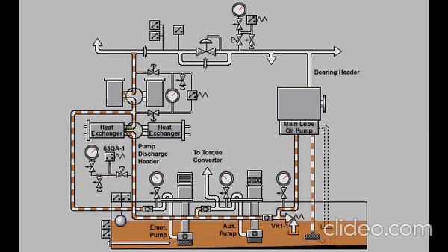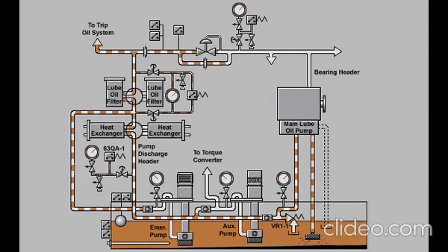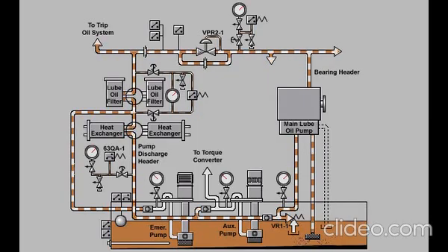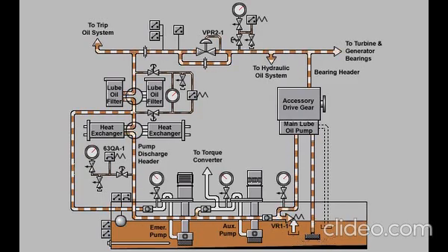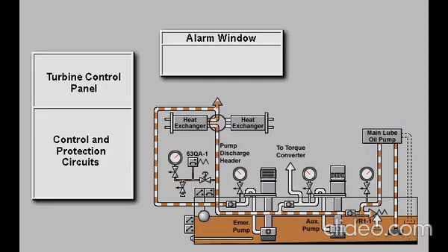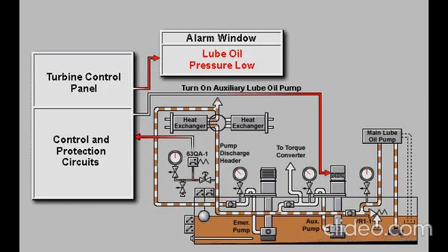Lube oil is cooled, filtered, and a portion is sent to the trip oil system. The remainder flows to the bearing header. VPR 2-1 maintains oil pressure in the bearing header at approximately 26 PSI. The bearing header then supplies filtered lube oil to the hydraulic oil system, the accessory drive gear, and the turbine and generator bearings. Should the lube oil pressure in the pump discharge header drop below 70 PSI, pressure switch 63QA-1 will initiate an alarm and activate the auxiliary lube oil pump. The auxiliary pump will remain on until it has been manually shut off at the motor control center.